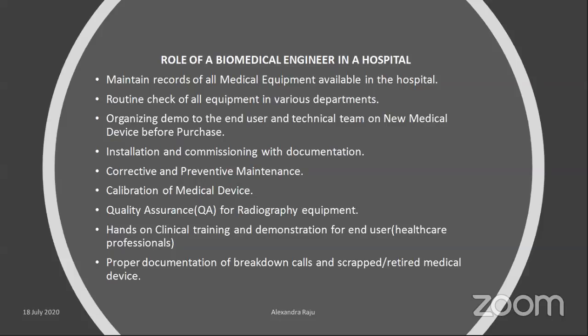The biomedical engineer has to organize a demo and a technical evaluation before the purchase. So organize a demo for the healthcare professionals regarding how to use the equipment and how to maintain the equipment. Installation and commissioning, with the documents, so installation and other documentation work, has to be done by the biomedical engineer. The preventive maintenance has to be taken care of by a biomedical engineer.